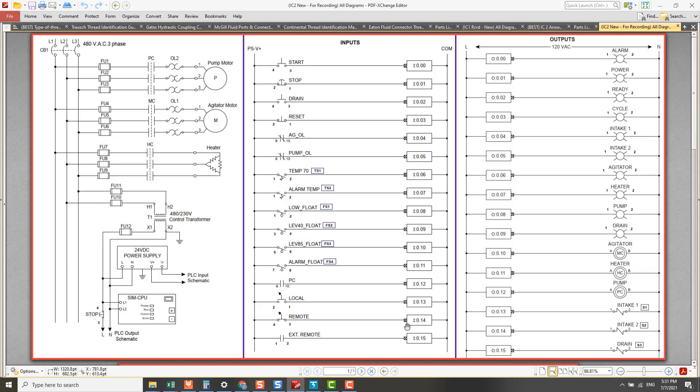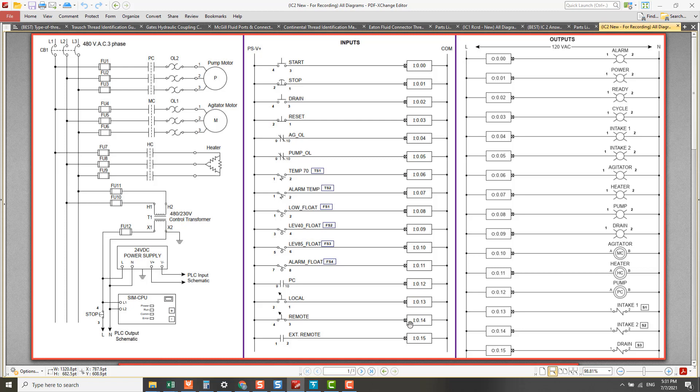So your LED is turned off. If your LED light is turned on, only two conditions are possible: Either the remote switch is internally short circuit or there's an earth fault here. Whenever there's a current flow through this channel, it will combine to this line which is a common line then short circuit to earth. That's why the LED status turned on. So which fault is it? Is it an internally short circuit for the switch or there's an earth fault somewhere around here? Let's check it out.